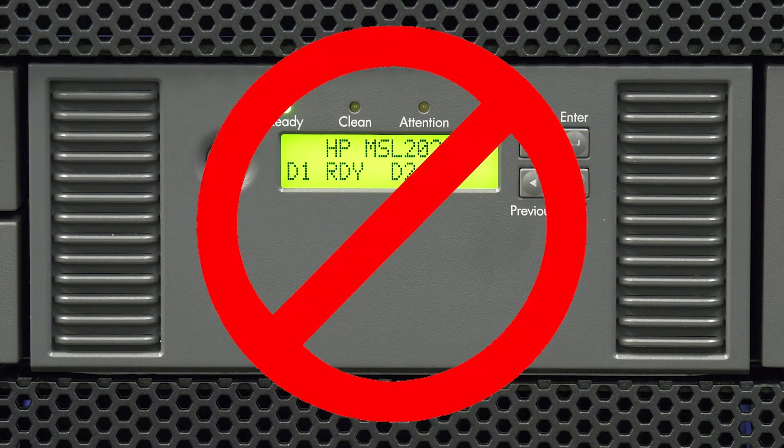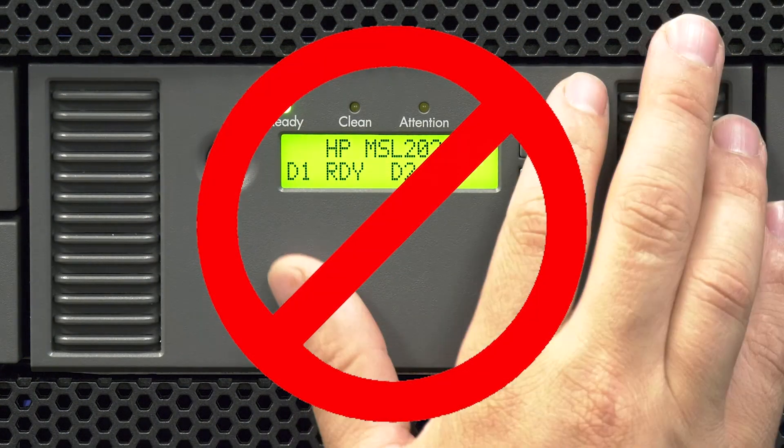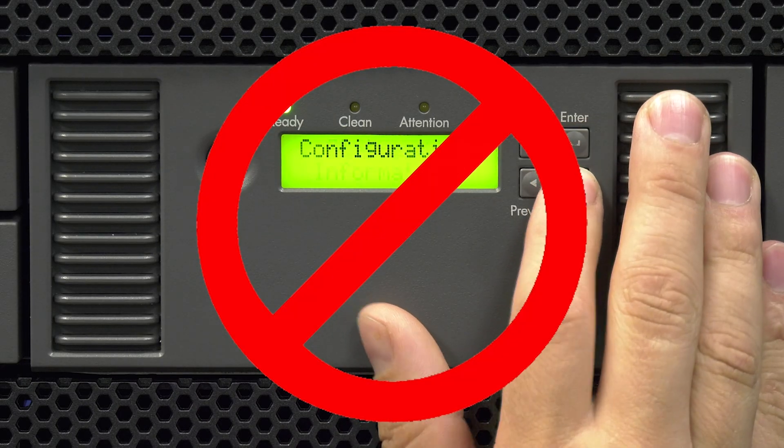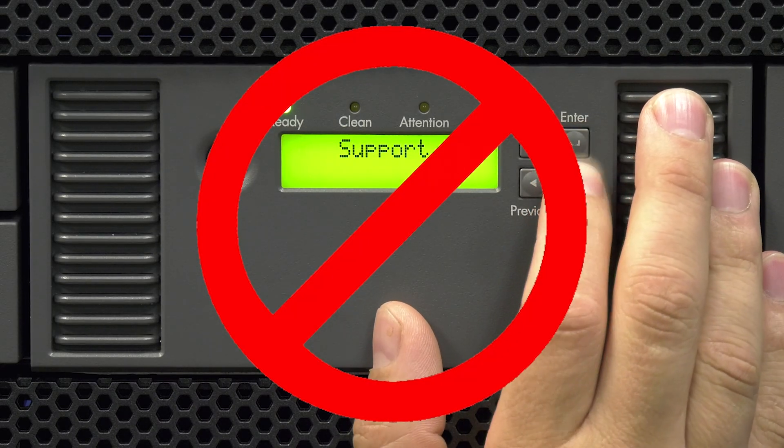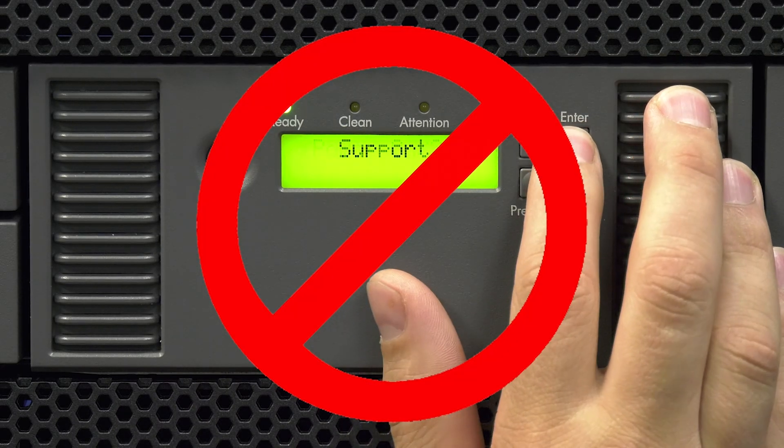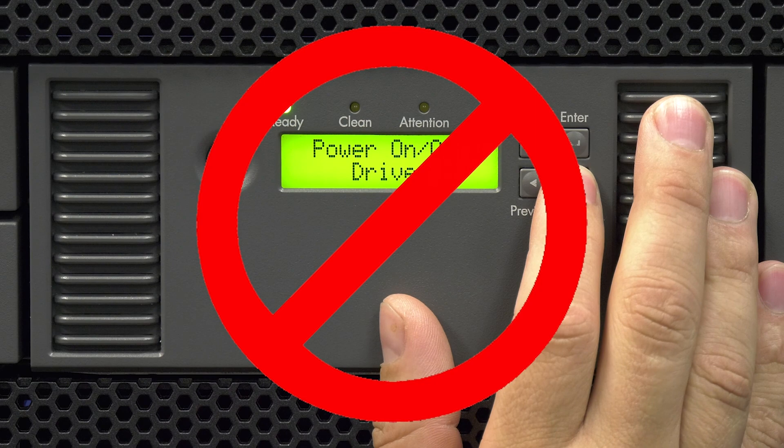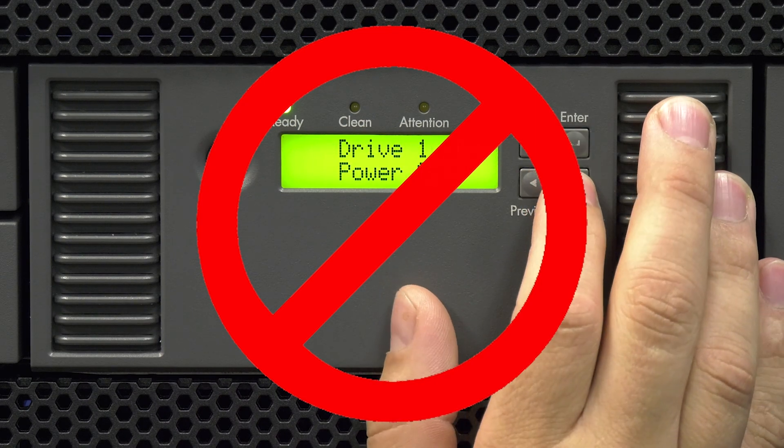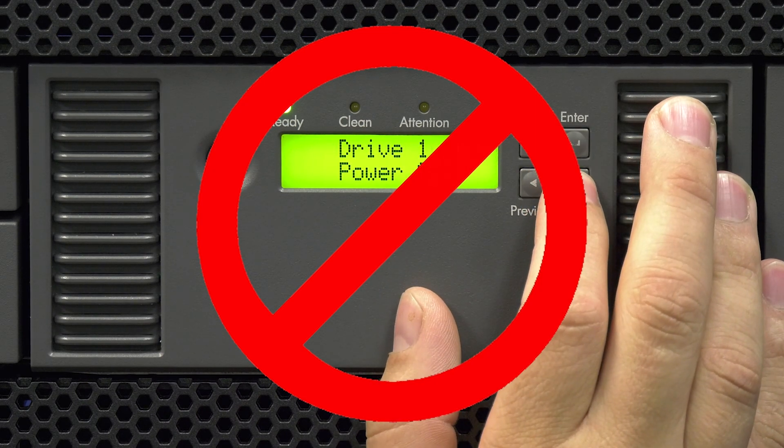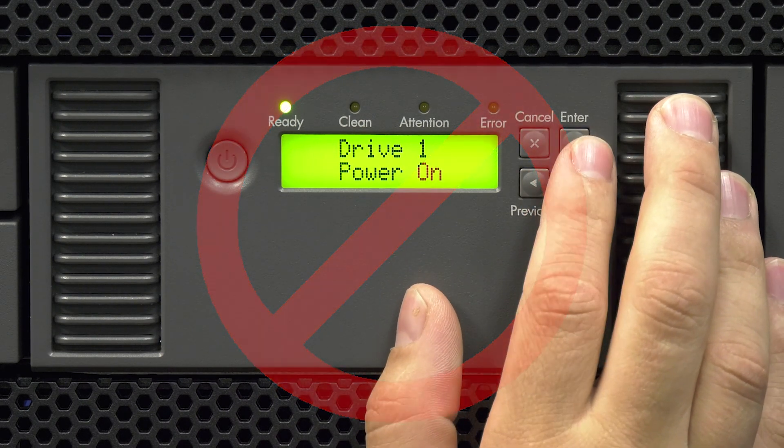in our experience this procedure more often than not causes the library to freeze completely and require a reboot. So, our best practices are to schedule downtime and power the library off to replace the drive.